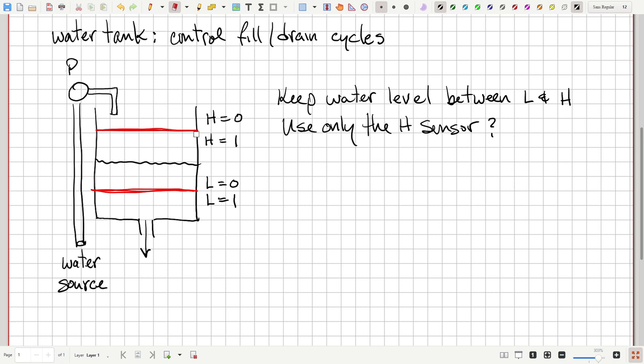And then as soon as somebody drains a little bit of water, you go below that level, right? Because it's just, in principle anyway, a point on the vertical axis. And so you would cycle the pump excessively. Of course, that would tend to burn out the pump, not be a very effective approach. So instead, we have two target levels, an upper and a lower. It's kind of like the dipstick in your automobile engine. You've got two dots, and you try to keep the oil between those levels.